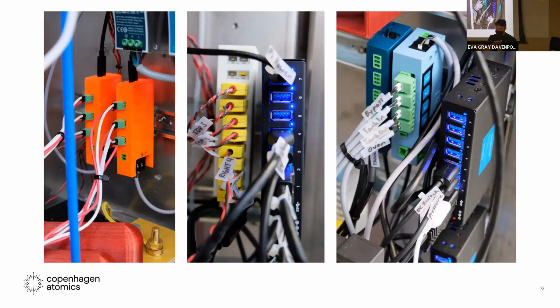In a reactor, we want multiple redundancies on sensors, actuation boards, and the control system. So we're implementing that now in the loops, with 5 to 10 Raspberry Pis doing consensus control on loop operation. They're all uploading data, so it's only an uplink, there's no downlink. If one falls out of consensus, the others continue working, and if one falls out of uploading data, it can buffer for a while and upload when it gets connection back. There's also an uninterruptible power supply that lets it keep uploading data and actuating control.